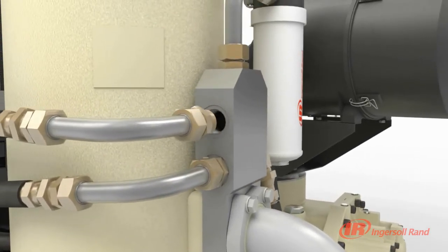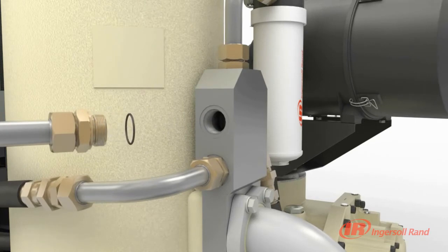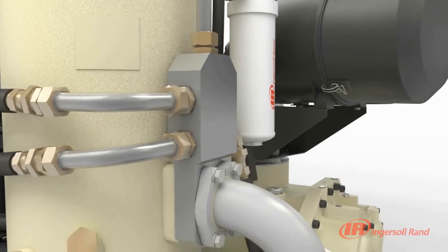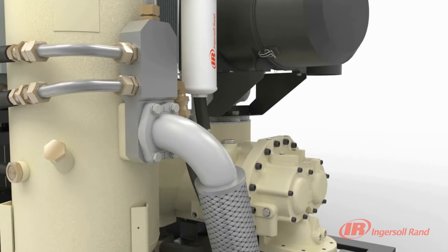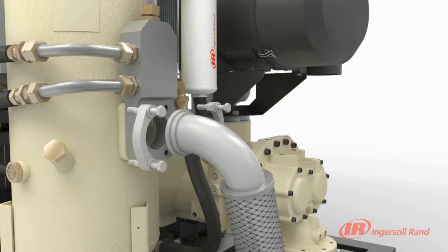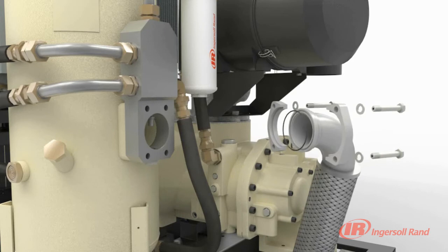Through the use of superior Viton elastomeric seals on critical connections, sealing reliability is significantly improved in a compact design. Because the sealing surfaces are flat and perpendicular to the connection, the elastomeric seals are compressed to form a tight, positive seal, virtually free of distortion. This O-ring face seal design allows for practically unlimited reconnections.